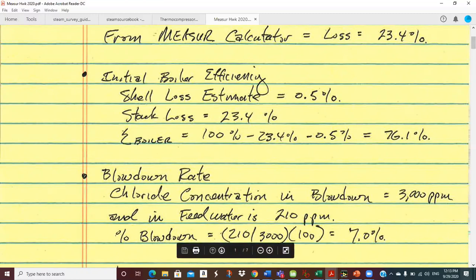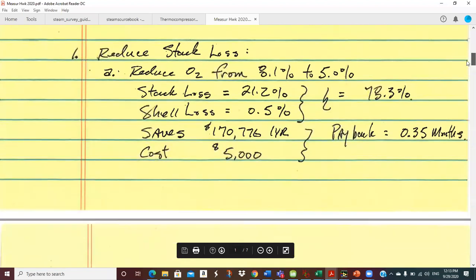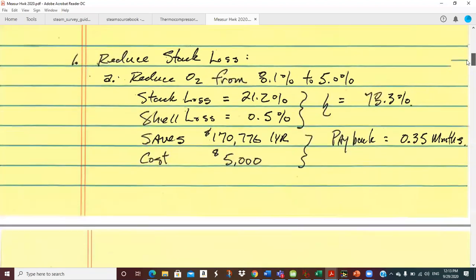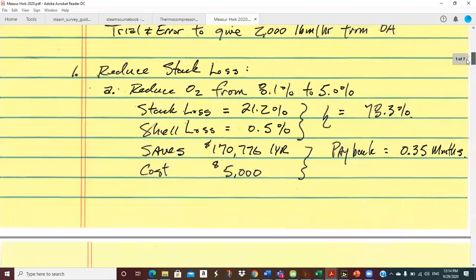We got hopefully a pretty good number on stack loss. Blowdown is actually modeled in MEASUR, so you don't calculate a blowdown loss and adjust the boiler efficiency for it. So I've got my initial boiler efficiency at 76.1%. That's my result.